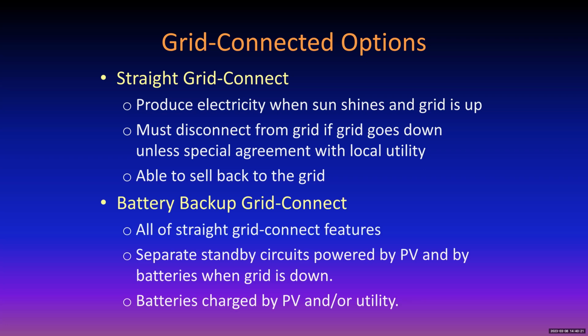The battery backup does all of what the straight grid connect does, but it also will disconnect from the grid and maintain a standalone and battery backup for the building if the building loses power from the utility, and that's historically. Now, the other part of the battery backup, again, since the year 2000, is that if you have an appropriate agreement with the utility, you can set it up such that you can turn your batteries on during grid peaking time and sell some electricity back to the utility. It may never make it out to the utility. It might just power the loads at your own occupancy, but that's just as good.